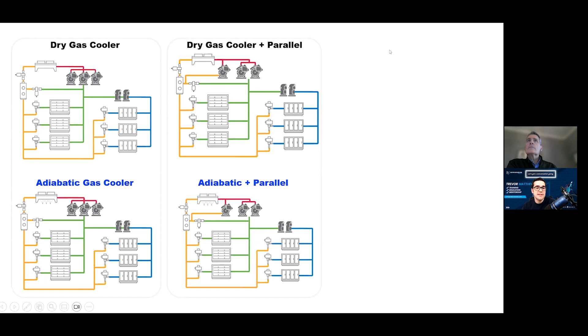So if we take a look at this central image here, Trevor, before I get to the chart, what you're talking about here is this parallel compressor is really being fed by excessive flash gas at a suction pressure that's typically 100 PSI higher than my medium temp suction. So really, that compressor has more compressor capacity now because the suction is higher. That's one thing. Its compression ratio has just been lowered. So that's a good thing because you have a lower total heat of rejection going into the gas cooler. And then the energy is less because the compression ratios are less.